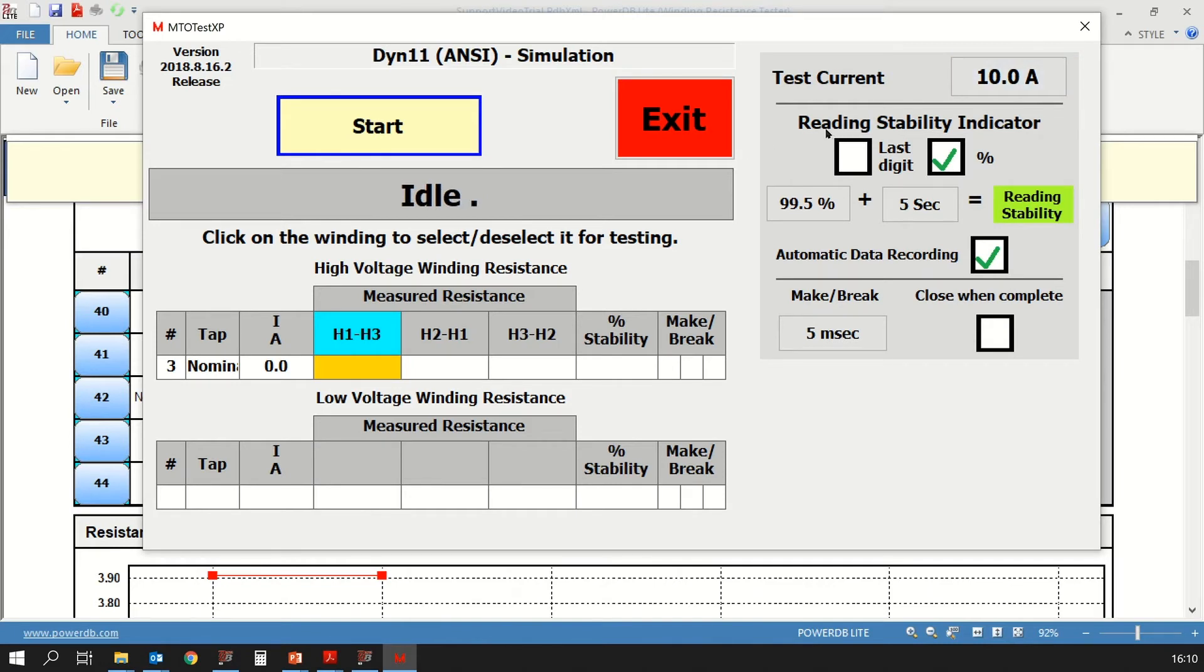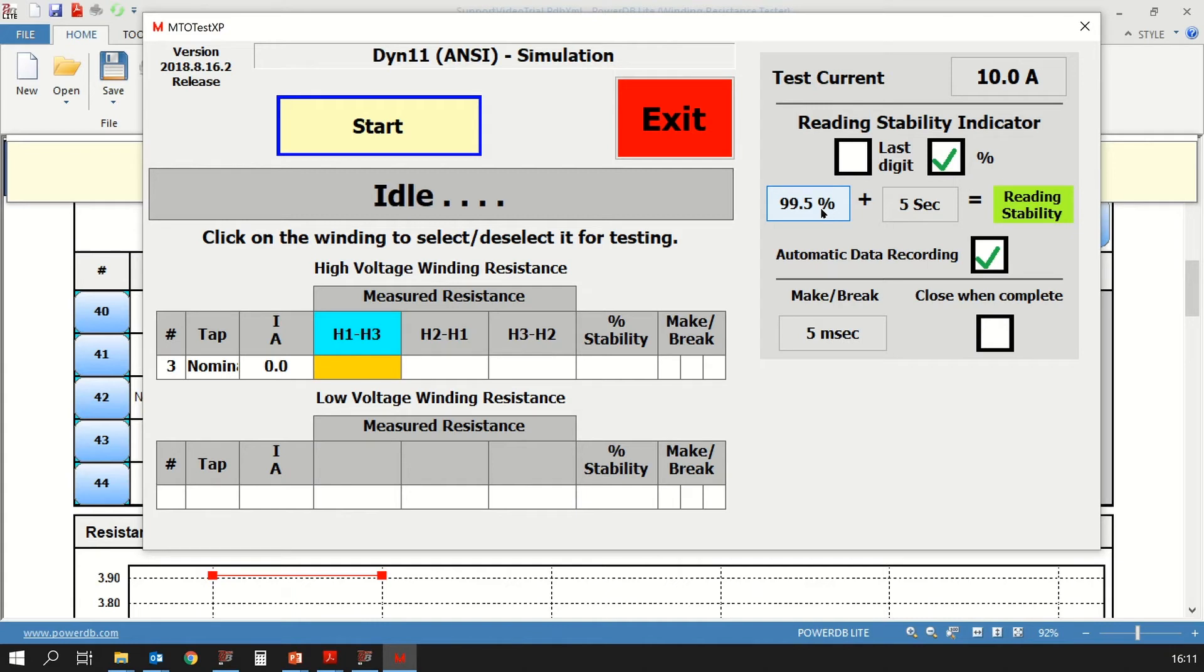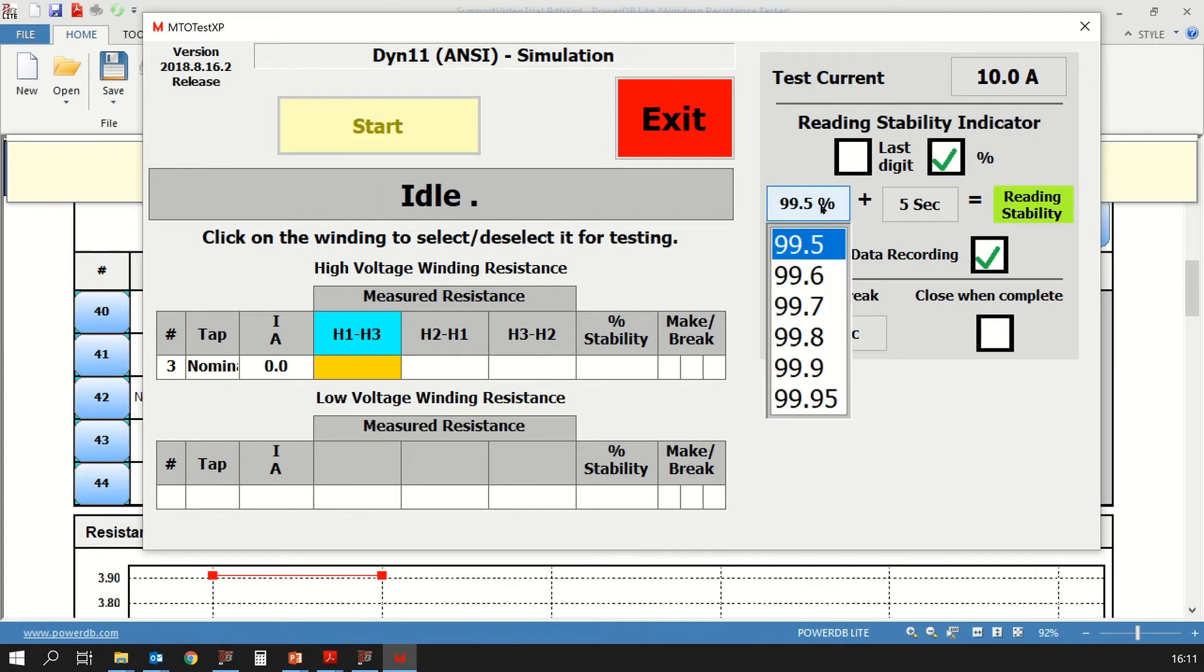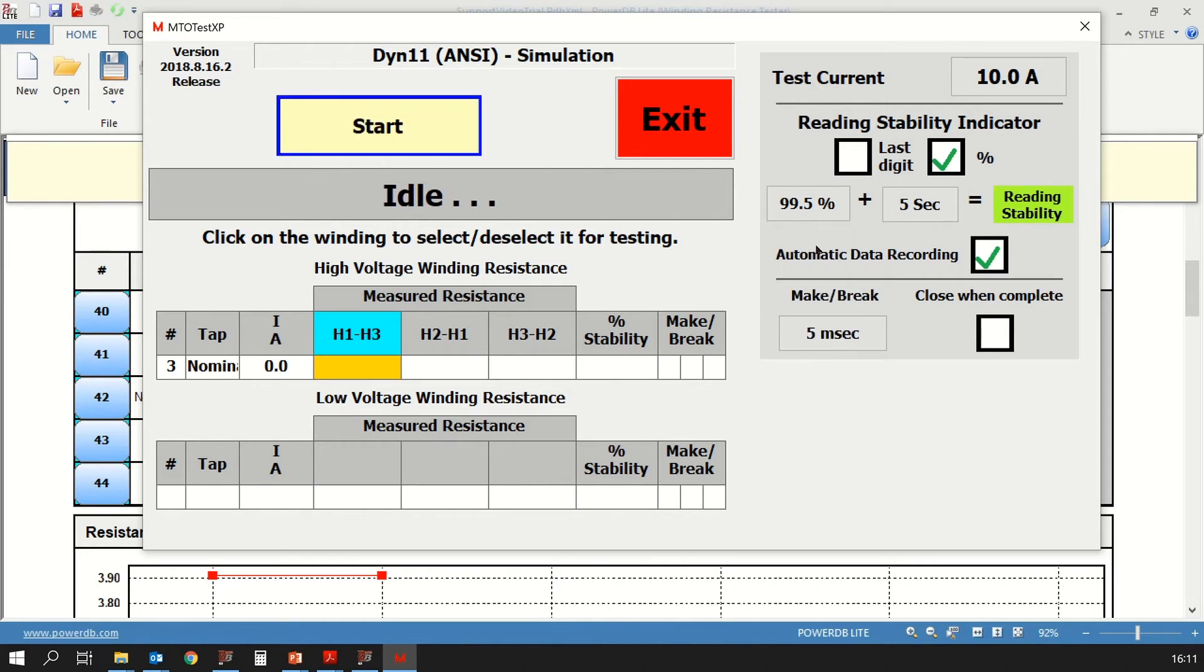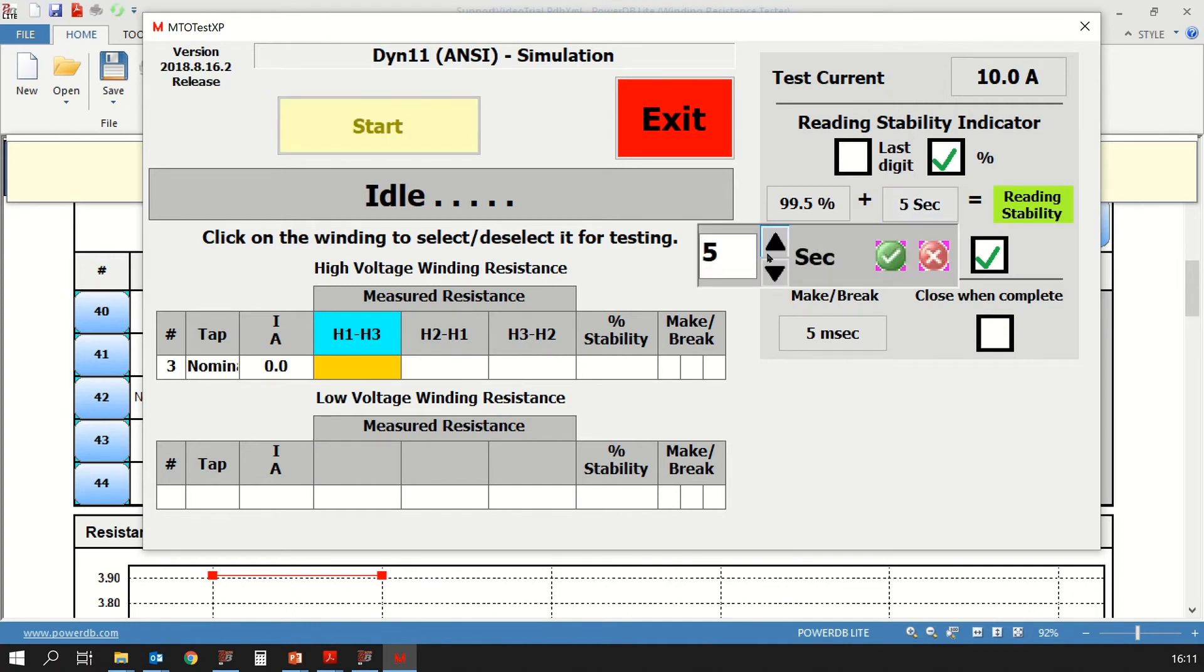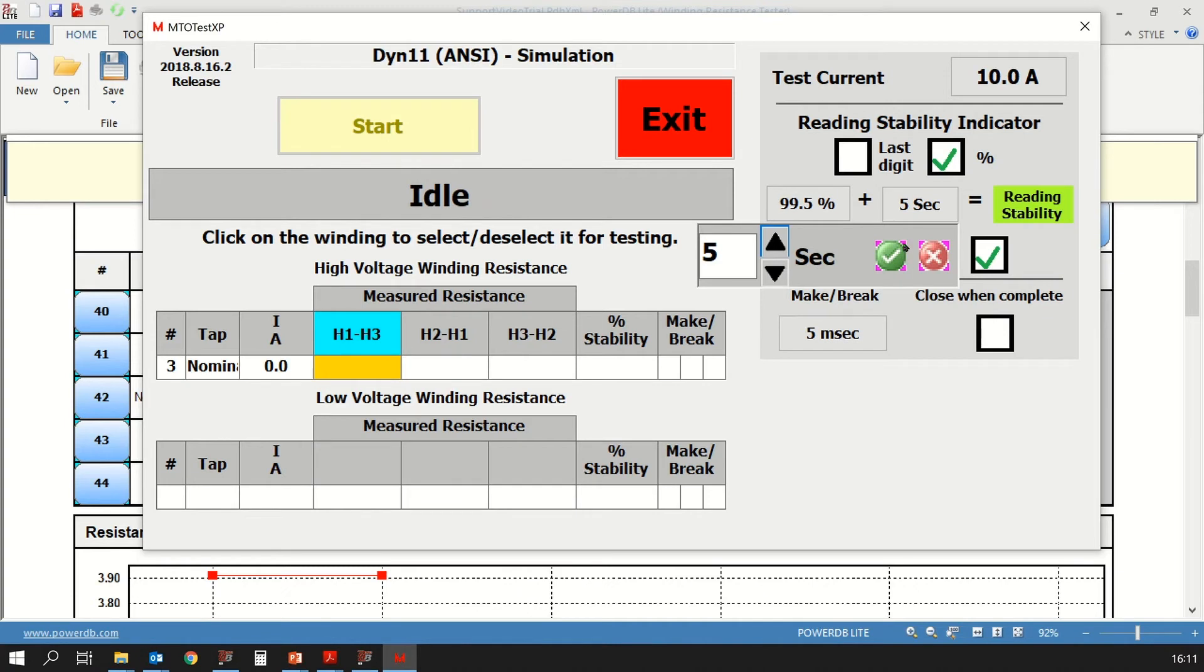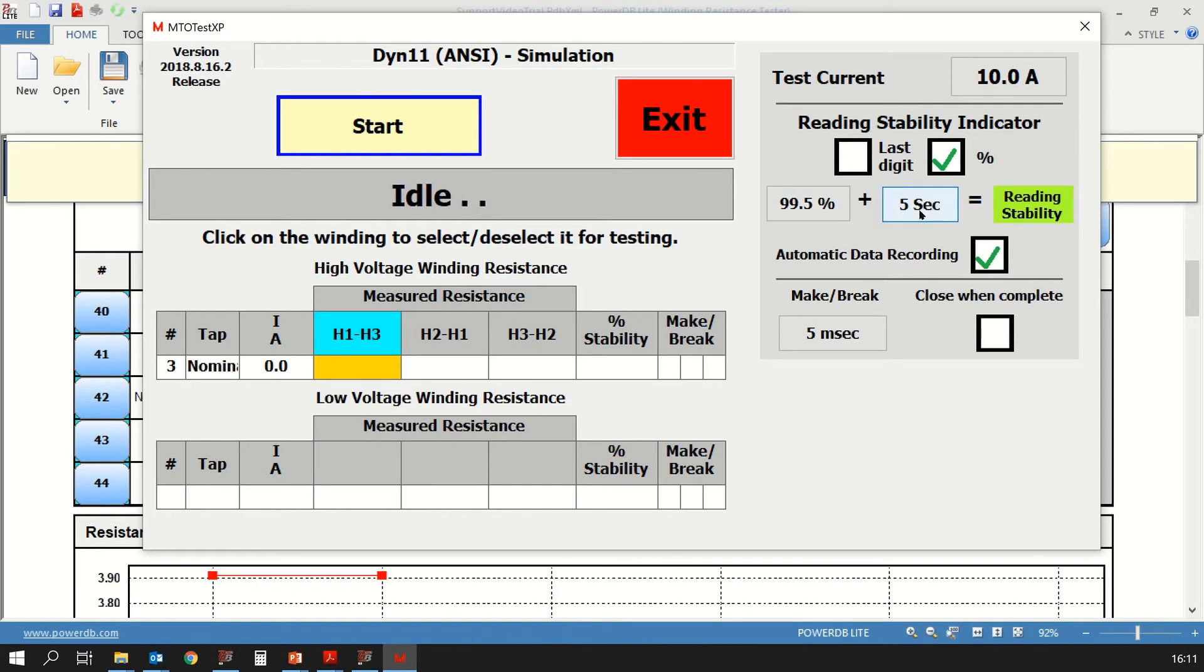Next, you have the reading stability indicator. You have two options to choose from. The first is the last digit of the reading, or you have a percentage stability. We are going to select the percentage stability. That value of percentage stability has been set at 99.5%. This percentage stability can be changed. If you click on it, you have different values, you can select from 99.5 all the way up to 99.95. We are going to let it be at 99.5. After the stability percentage has been reached, you want the reading to not change for a particular period of time. That period can be selected to be five seconds or six seconds or even four seconds based on what your requirement is. I'm going to leave it at five seconds and then click on the green check mark box. The reading will become stable if the reading is 99.5% stable and that happens for five seconds.